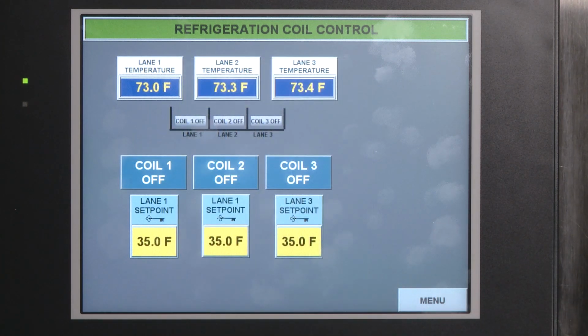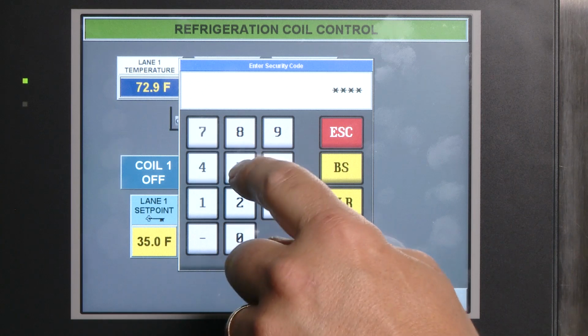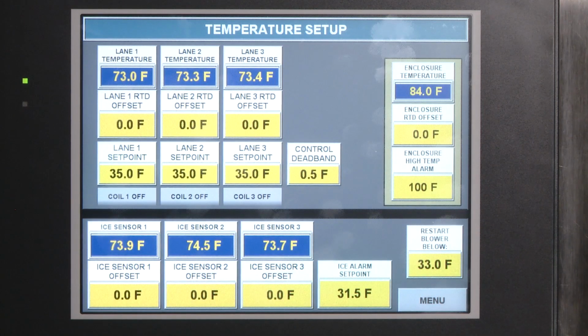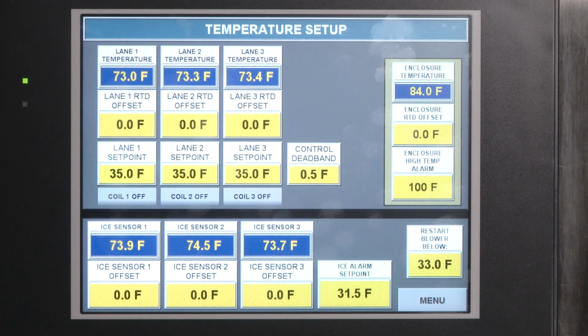Offset is the only temperature adjustment. The correct value of the temperature sensor can be changed to correct the reading of the temperature sensor if it has a reading error. The correction can be a positive or negative number. The deadband prevents rapid chatter of the refrigeration valves. It is subtracted from the set point to create a shutoff value.